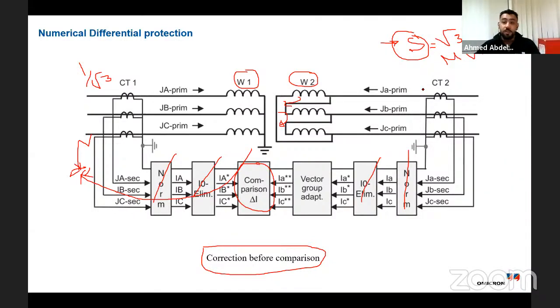Then the vector group compensation, or the vector group adaptation. You will see here, the vector group adaptation happens only on the delta side. It doesn't happen on the star side. And here, I need to go back to the same point. I need a reference. Usually 99.9% of protection relays need a reference, which is the star side. So I will say that the star side is my reference winding, and I need to bring the delta side current and rotate it back to the star side to avoid the phase rotation or angle that happens due to the vector group.